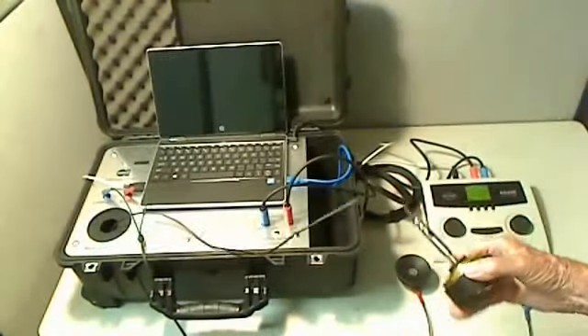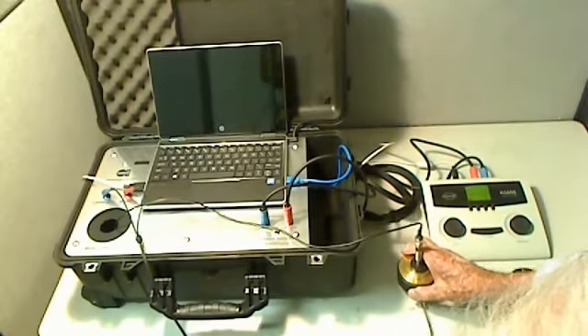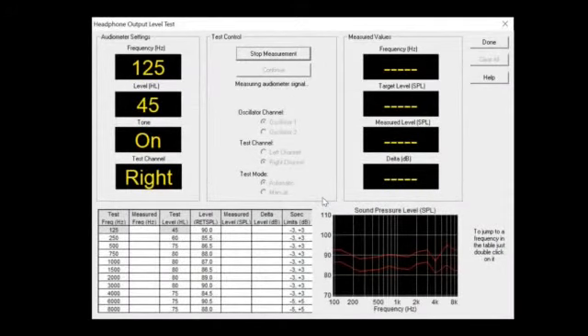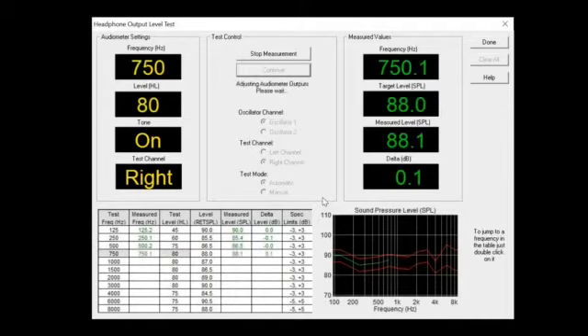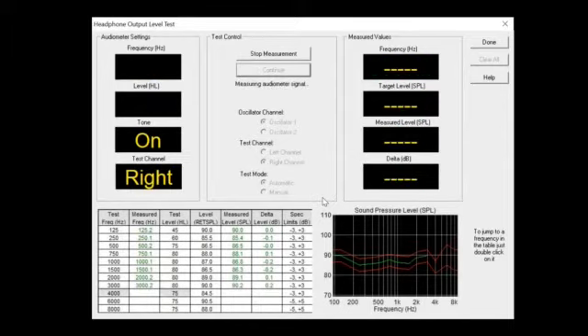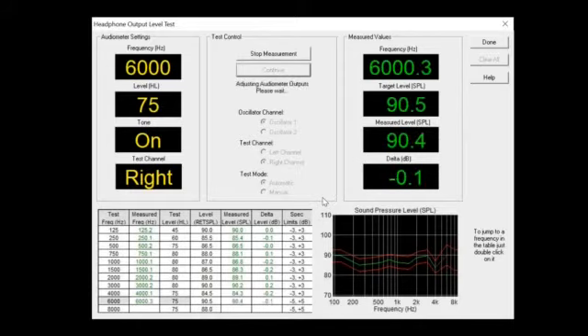I'm going to take the coupler, bring it over here, and place it onto the right headphone, making sure that it's properly seated. So I click on OK. Guess what? We're in control. The computer has taken charge of this information, and it's going to continue on doing this until it's finished, or until you get some more commands. Now, unfortunately, I think I have to do something here. Unfortunately, we've done this audiometer many times before, and it's all within calibration. Every time we get an ACS system in for service and update and calibration, we go through several tests before we send it back to them.